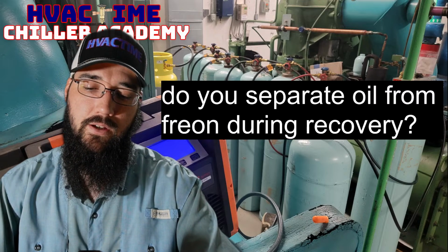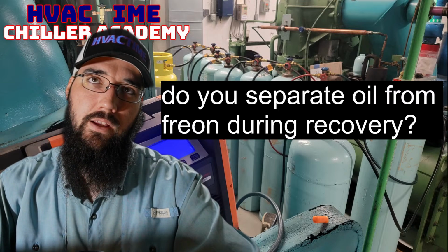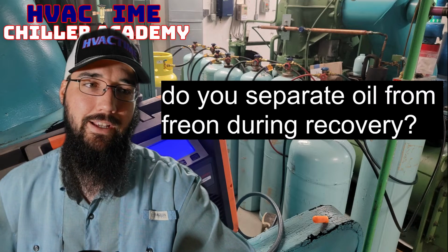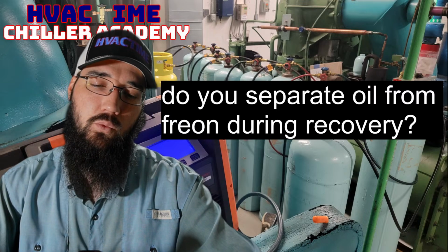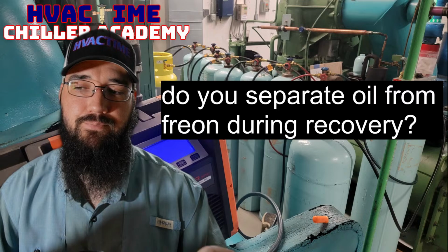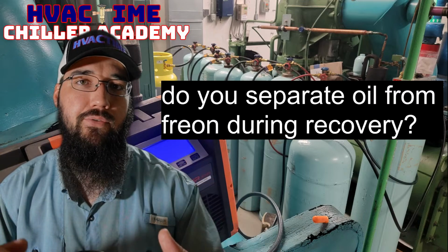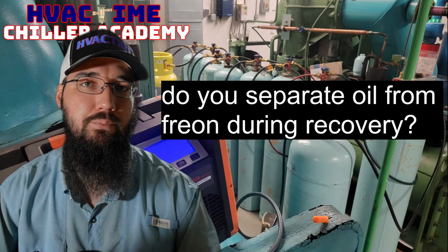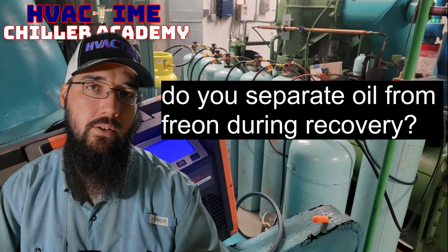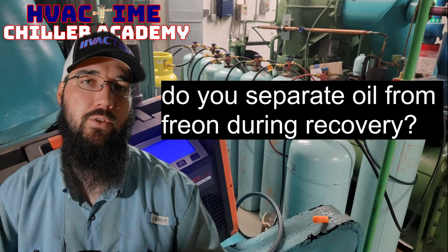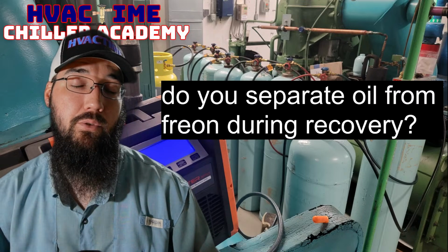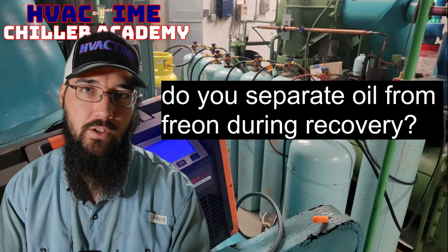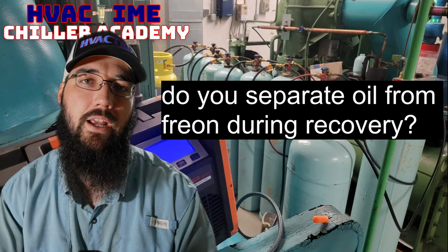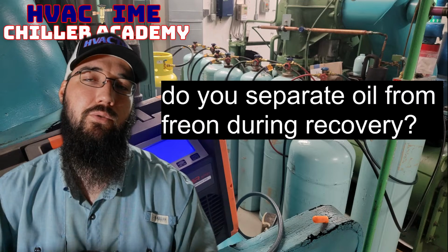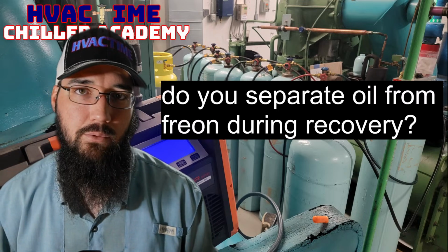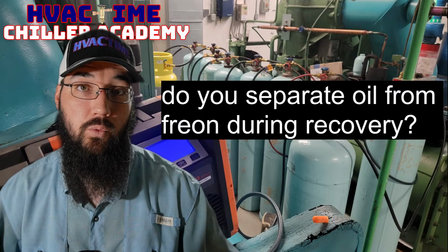In some cases, if we are worried about oil contamination in each tank, what we've done is recover down until we know we've got just a few inches or maybe a foot left in the bottom of the cylinder, and then pull that back off as vapor. That way, whatever oil may have stacked on top, we can make sure the refrigerant is vaporized back out of it, because the oil is going to stay in its liquid state, but we can flash the refrigerant out into a vapor and still get it back out of that oil. That is one way to separate those.